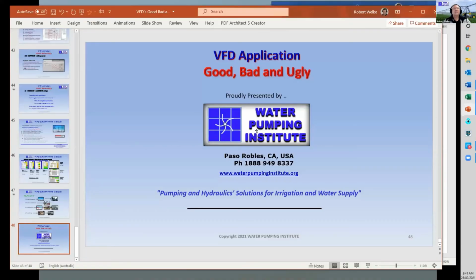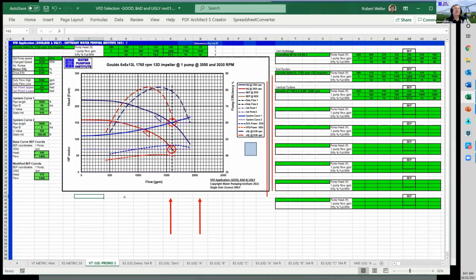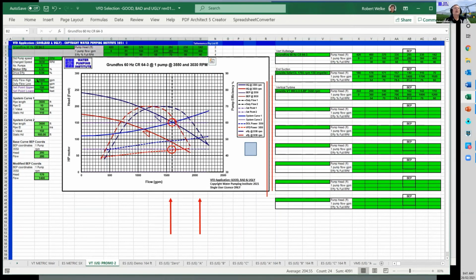Let me just go back to the spreadsheet, and I'll show you a couple of extra features. We can drag over, for example, if we want to change the pump, we can just copy that whole amount there and drag it and put it over to here. And we've changed that pump. It was a Goulds vertical turbine. Now it's a Grundfos 60 Hertz. So you can build up your own library of pump curves on the right. But the beauty of it is you can change the configuration of the pump.